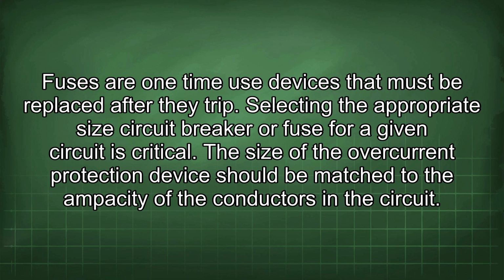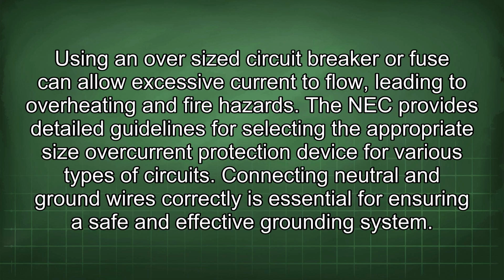Selecting the appropriate size circuit breaker or fuse for a given circuit is critical. The size of the overcurrent protection device should be matched to the ampacity of the conductors in the circuit. Using an oversized circuit breaker or fuse can allow excessive current to flow, leading to overheating and fire hazards.